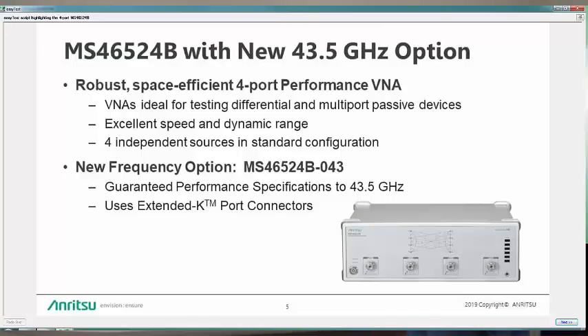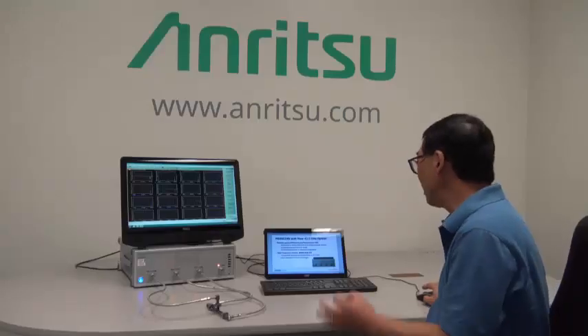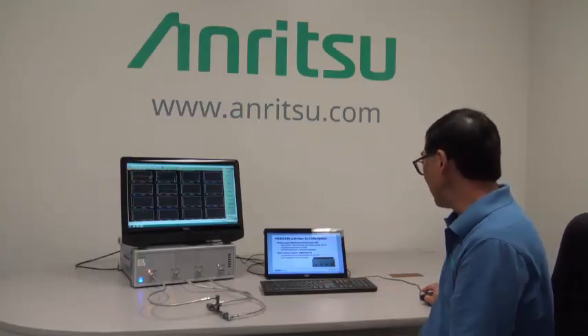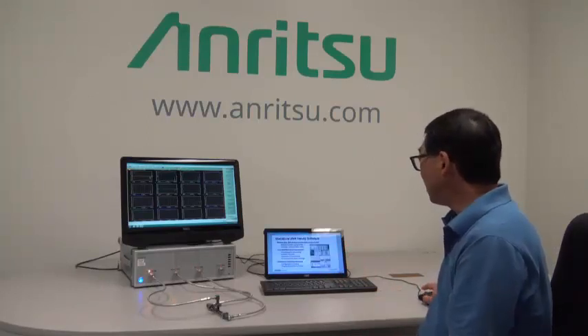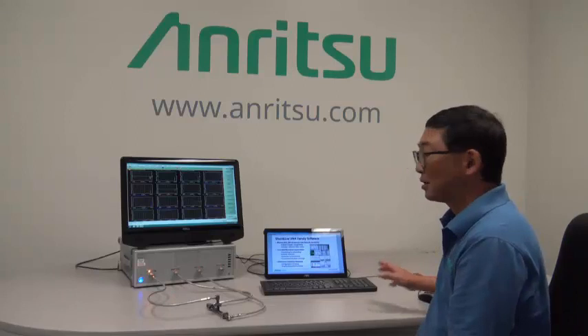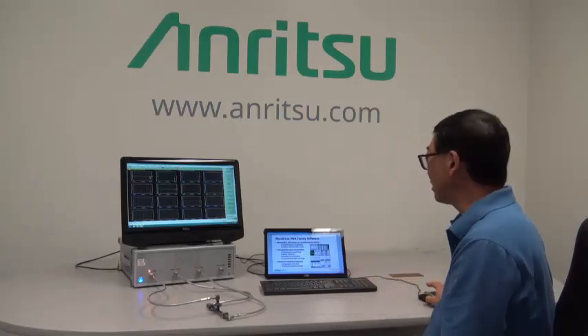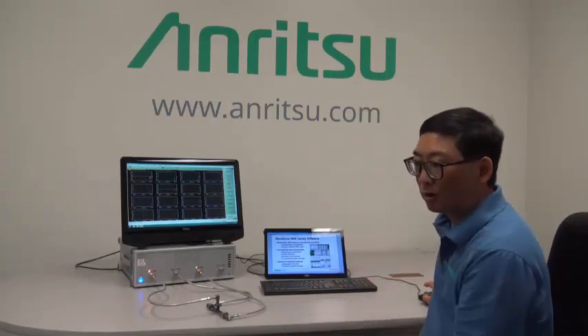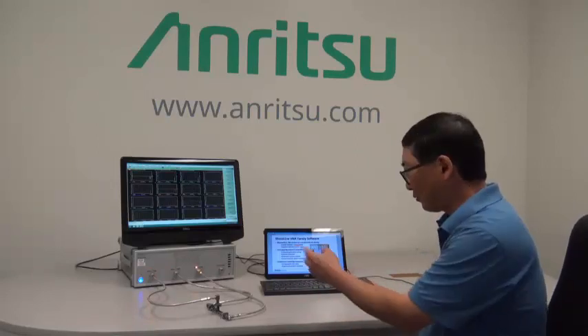Here we're just highlighting the fact that we're running on a 4-port MS46524B 43.5 gigahertz VNA using the ShockLine family software, which is shared across all the different ShockLine VNAs, from our 1-port 121 all the way up to the 4-port.